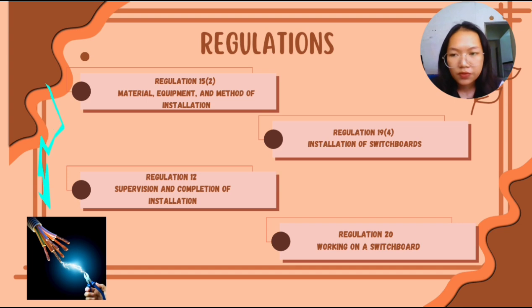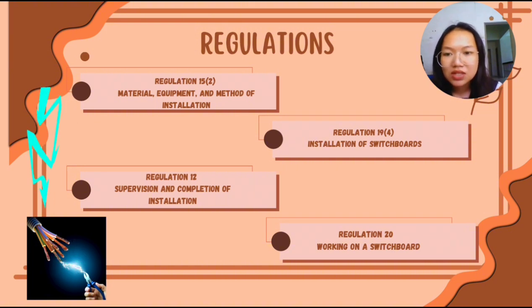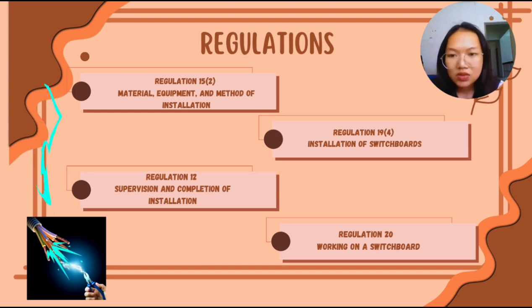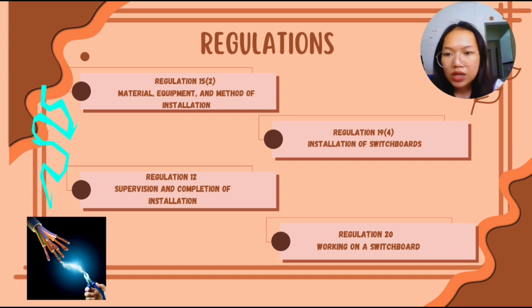Regulation 15 covers material, equipment, and method of installation. The cable must be insulated and protected to prevent dangers. Using uninsulated cable increases the risk of accident. And Regulation 19 covers installation of switchboard. Only a competent person or those supervised by them can work on a switchboard. Supervising unqualified workers without proper oversight breaks this rule.